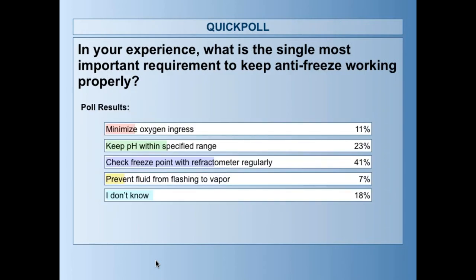Minimize O2 ingress. Yeah, you certainly want to do that. Either you want to keep the oxygen from getting in there to begin with, or maybe put an oxygen scavenger like a sulfite or something in there that will absorb any oxygen that might be getting through the wall of your tubing or around your pump seals and stuff like that.